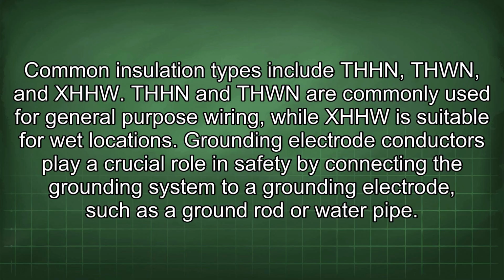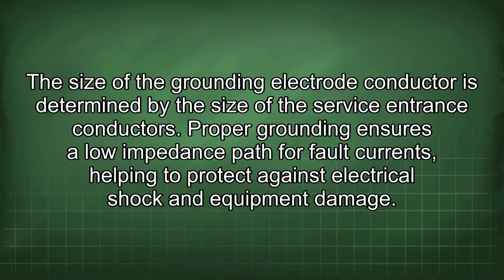Grounding electrode conductors play a crucial role in safety by connecting the grounding system to a grounding electrode, such as a ground rod or water pipe. The size of the grounding electrode conductor is determined by the size of the service entrance conductors.